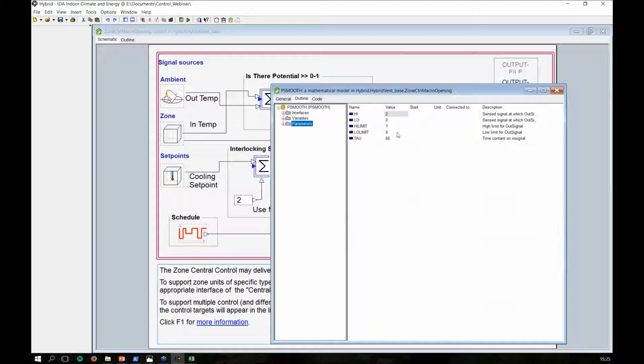My third condition is interlocking set points. So when I open a window, I want to make sure that my mechanical ventilation is not affected. So the first thing I would want to do is turn off my mechanical ventilation. But the second thing I want to consider is, what if the potential out there is not enough? There is a 2 degree difference, but what if the wind speed, for instance, or the internal gains are too high? Then at some point I would want to close this and start the mechanical ventilation.